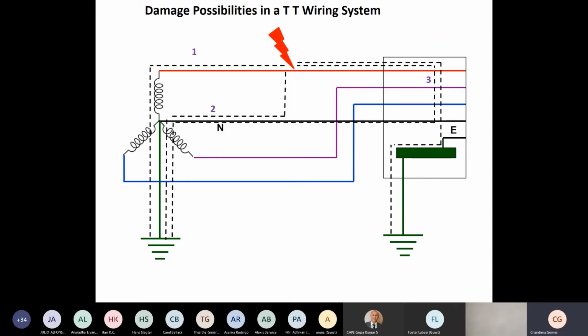This is very common in countries where the TT wiring system is practiced, especially if the transformer which is feeding your building has quite a high earth resistance at the star neutral point, and if your building has quite a low earth resistance. Usually we say that your earthing system should be quite low, but this is one of the negative sides of that as well. There may be an arcing from line to earth. Usually it happens inside the main panel, where the main panel gets blasted, or it can happen inside an equipment, in which case your equipment will definitely experience a catastrophic failure. Okay, so in most of these cases where you see a red color circle or ellipse, there is an arcing. The blue color ellipse shows you a melting.